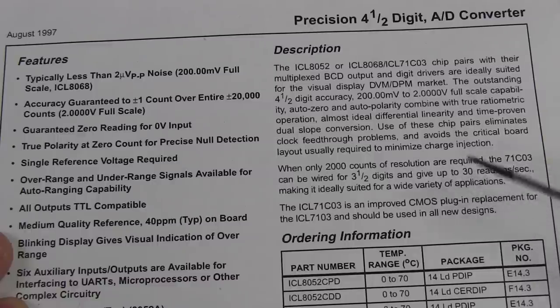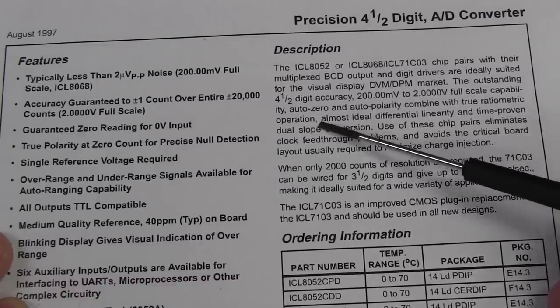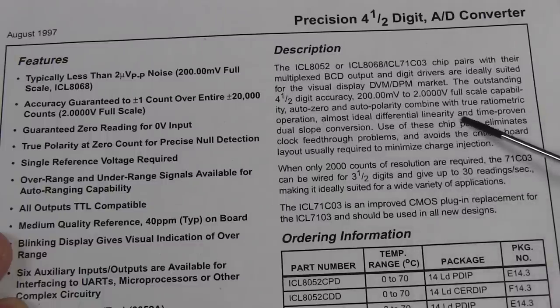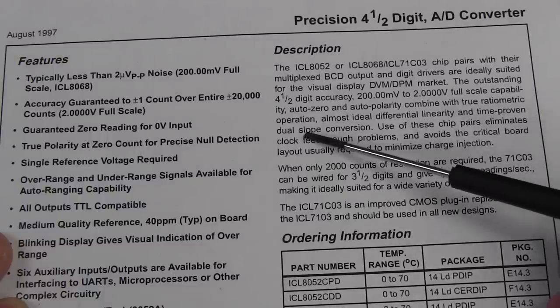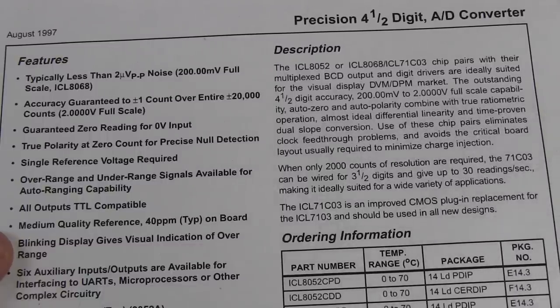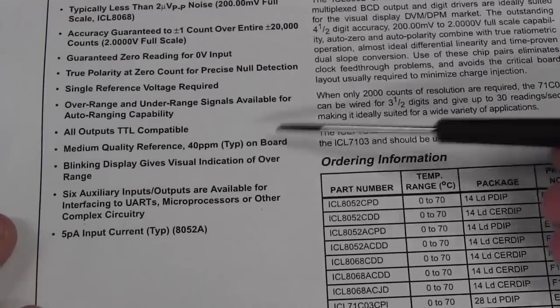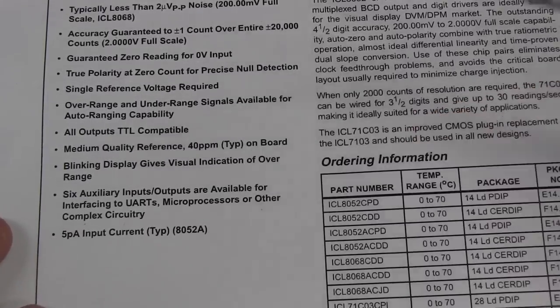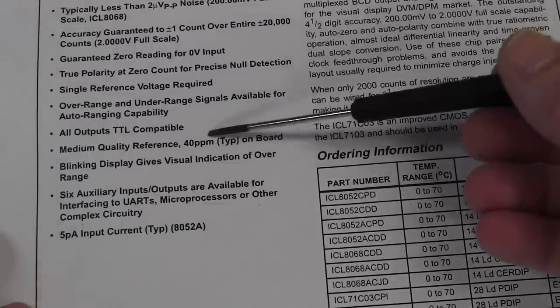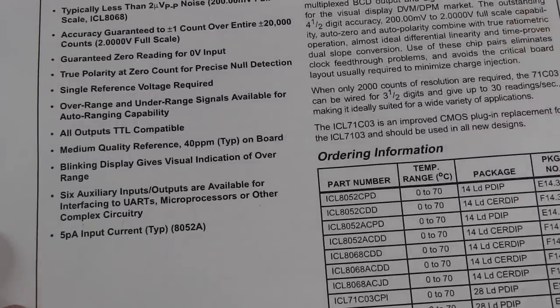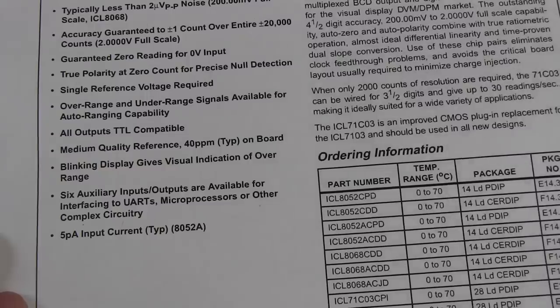And it also does a 3.5-digit mode, which is what's used here. And you can get up to 30 readings per second to do that. And I love here how they're tooting their horn. Almost ideal differential linearity and time-proven dual-slope conversion. Love it. It's got a medium-quality reference in it. Not a high-quality reference, it's a medium-quality reference, 40 ppm. Yeah, not that terrific. But more than good enough for this.